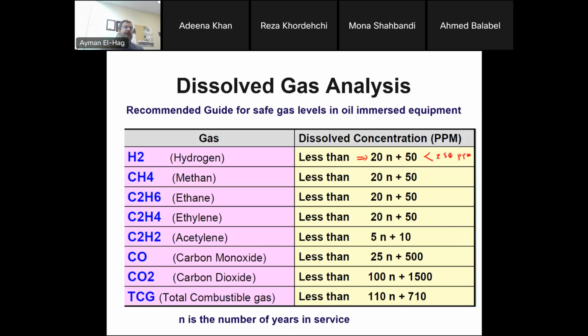Again, because there is no existing severe fault in the transformer oil, the values can be relatively small, and you can tolerate some increase with aging, because faults happen in the transformer from time to time. Now, yes, there is an online monitoring technique, but before, you took a sample basically every year or every other year. So there might be something happening in between, something not severe, by the time you took the sample, and the residual of those gases can still be there. Now with the online monitoring system and DGA, things have changed a little bit. Now they know in real time what is happening.